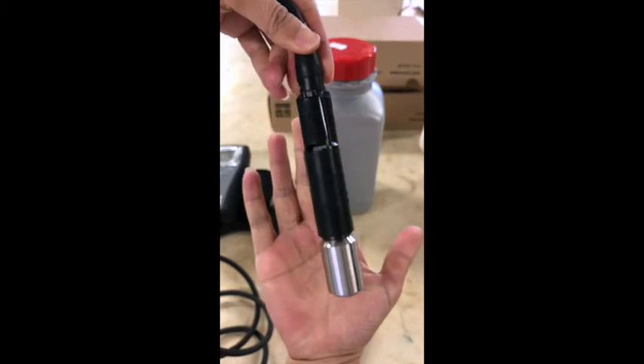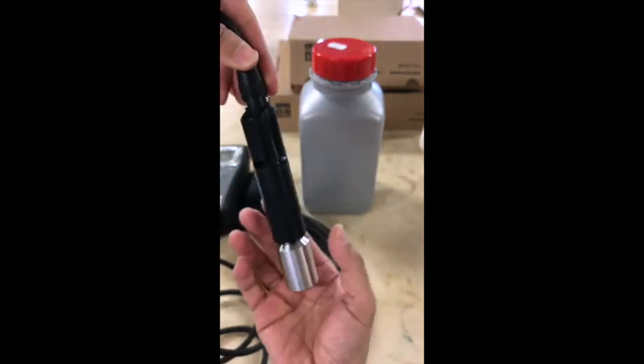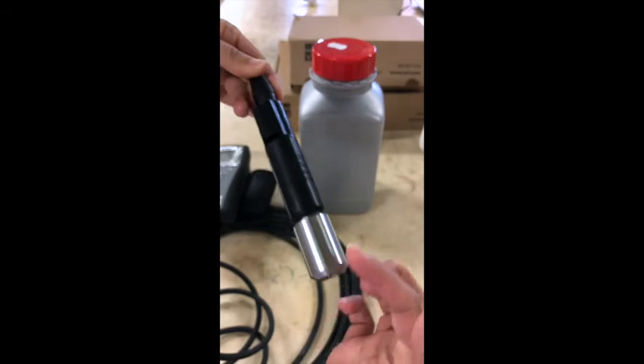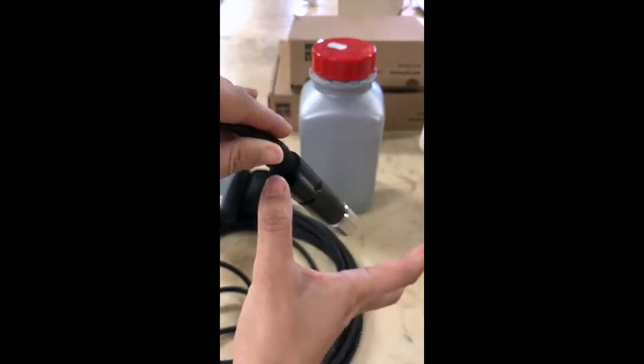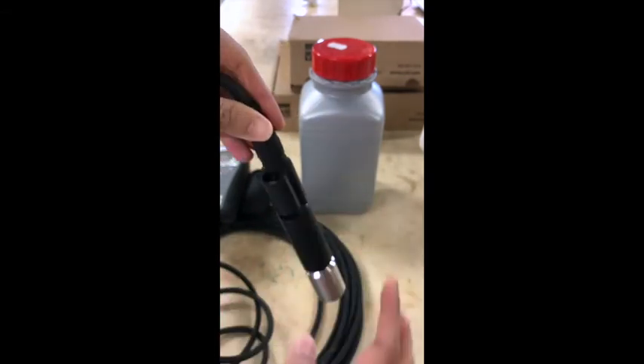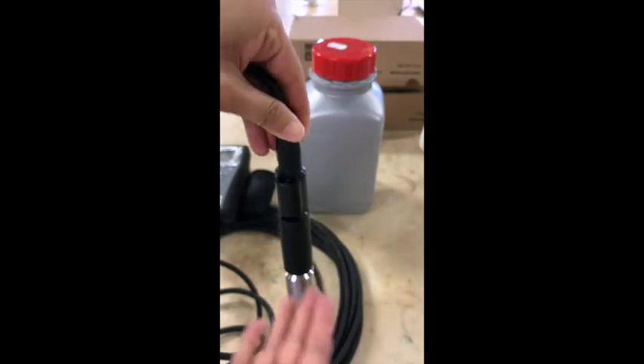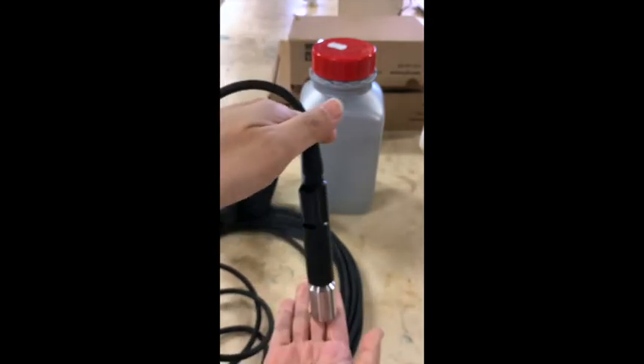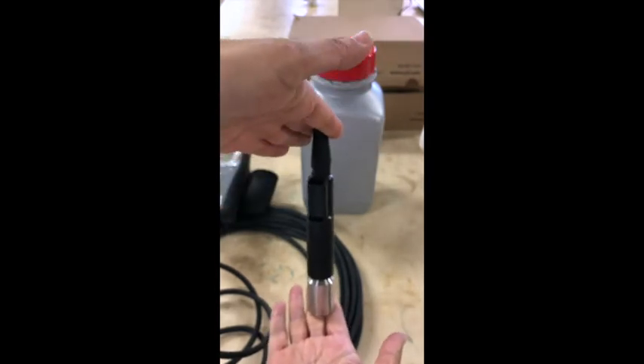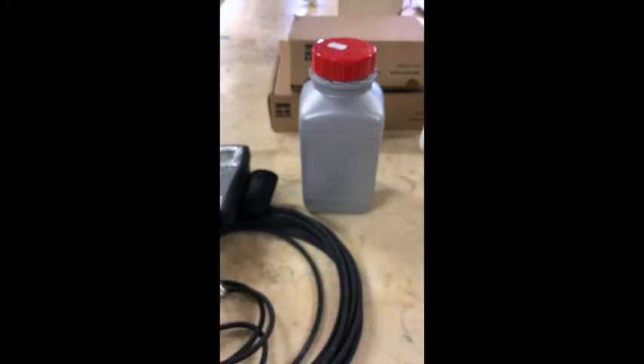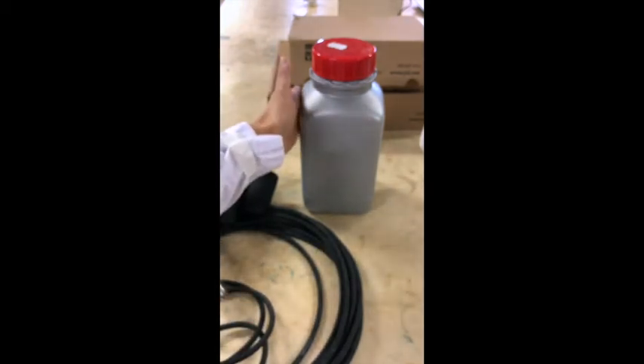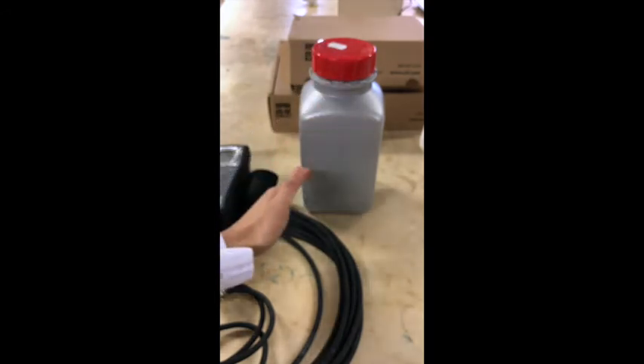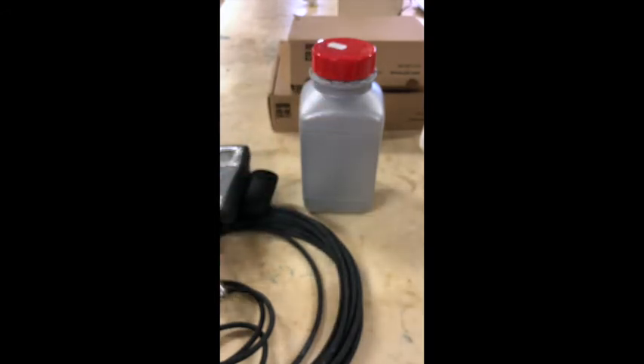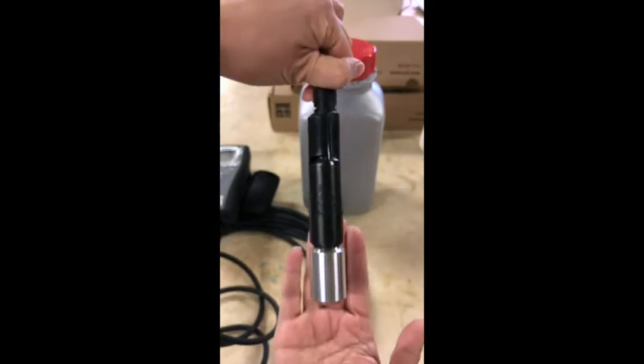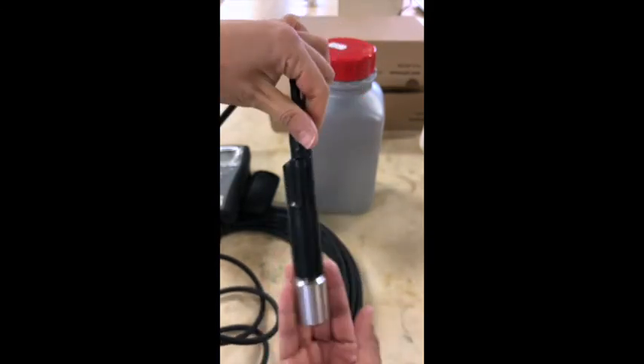And now I will introduce the probe of the conductivity meter. Conductivity will be measured from the tip to the holes of the probe. That's why the whole probe should be immersed into the sample being measured. It requires a certain depth of the water sample. That's why we place the seawater sample inside a large reagent bottle, and then we put the probe inside the bottle.